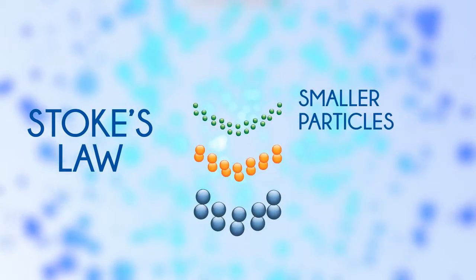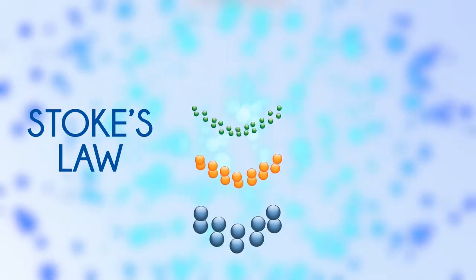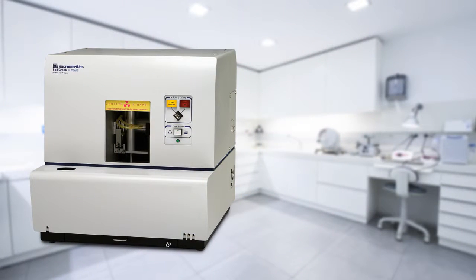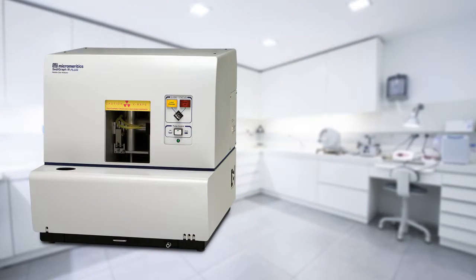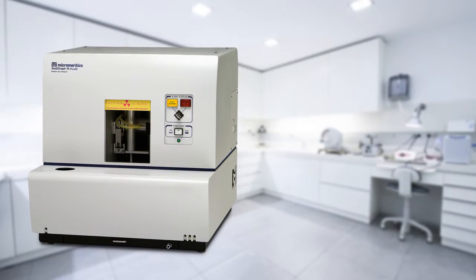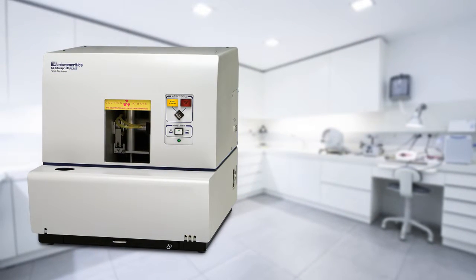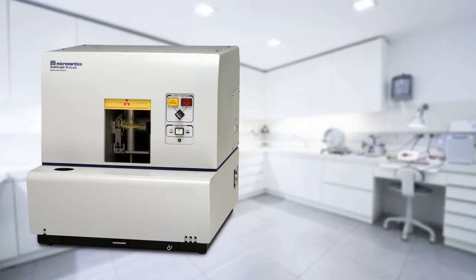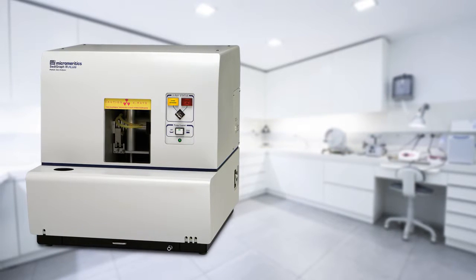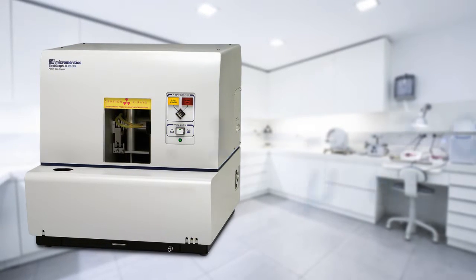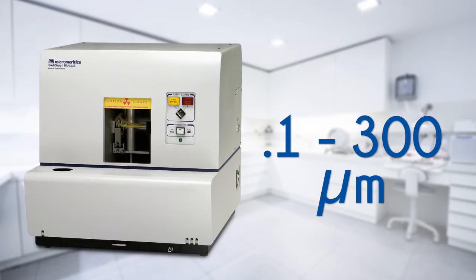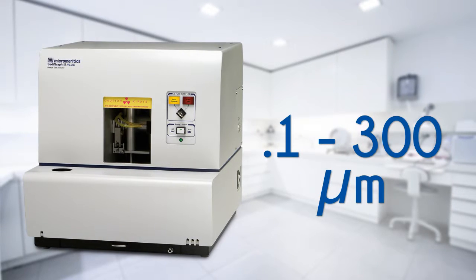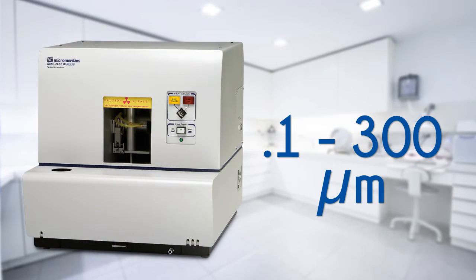The SediGraph III Plus uses x-ray absorption sedimentation analysis to provide high resolution distribution with a particle size range of 0.1 to 300 micrometers for complete particle accountability.